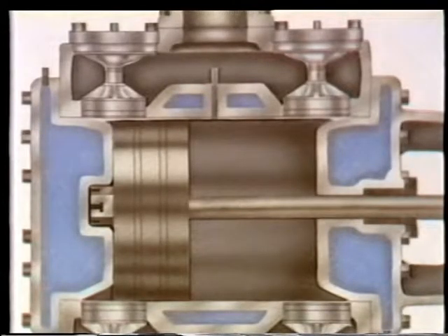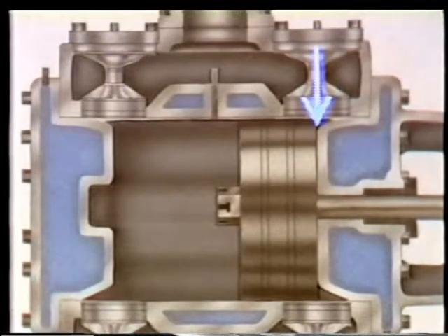This brings us to another critical point in the reassembly procedure, adjusting the piston end clearance. Piston end clearance measurements are taken at two points, between the top of the piston and the top head, and between the bottom of the piston and the bottom head.